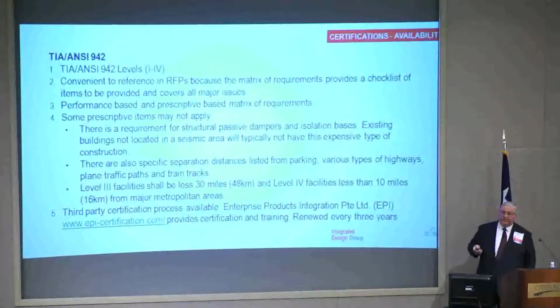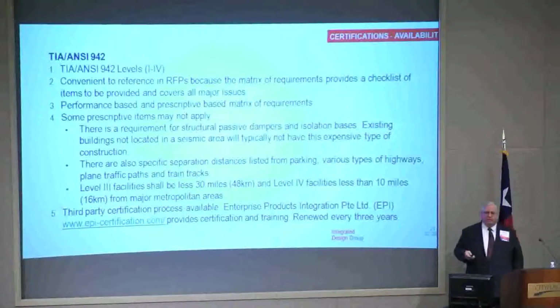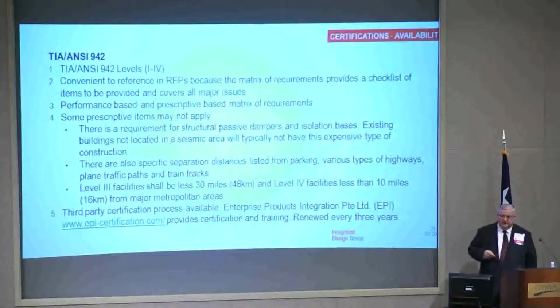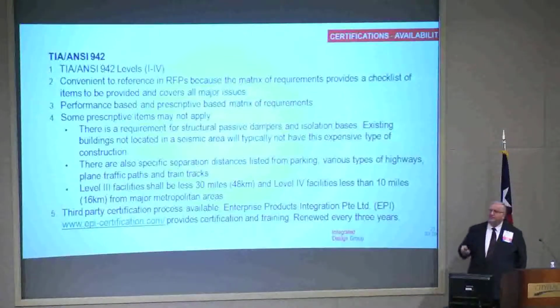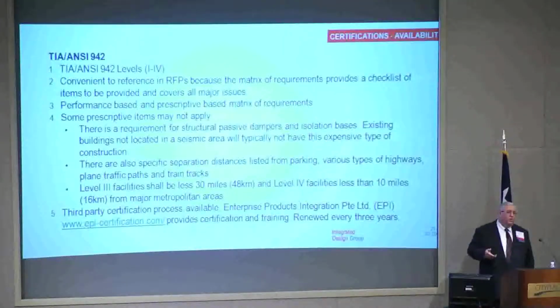TIA ANSI 942 is another standard that's out there. This one is an ANSI standard as well as a TIA standard. We see this a lot in government specifications and also overseas specifications. It's nice and easy, it's a matrix, it's a checklist. It makes it very easy to say you've got to have this, this, this, and this to meet this tier. The problem you sometimes run into is it asks for requirements that don't apply to your project.